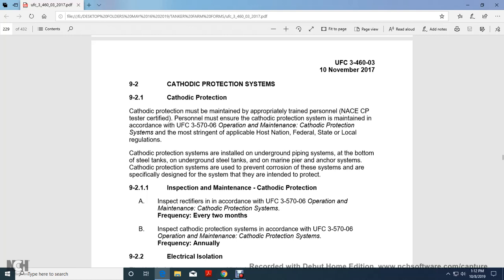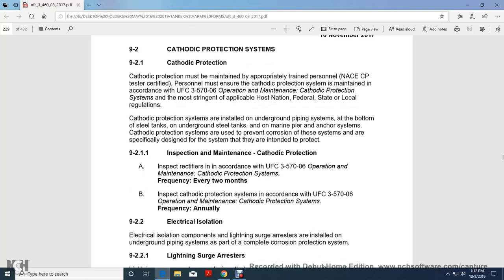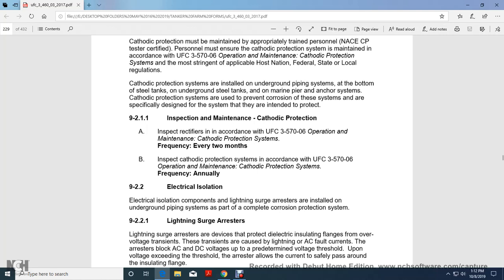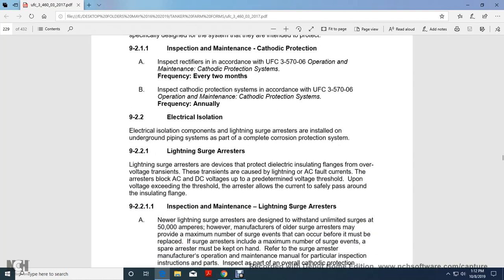Cathodic protection is used to prevent corrosion of these systems and is specifically designed for the system it is intended to protect. Inspection and maintenance of cathodic protection: inspect the rectifiers every two months in accordance with UFC 3-570-06, Operation and Maintenance: Cathodic Protection Systems. Inspect cathodic protection systems annually according to the same UFC.